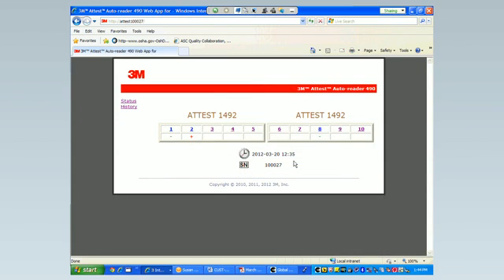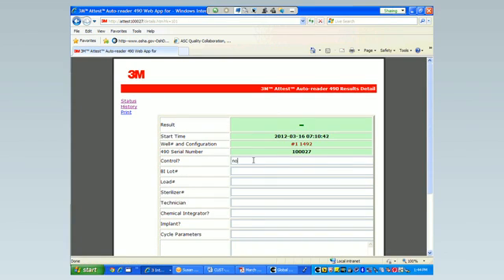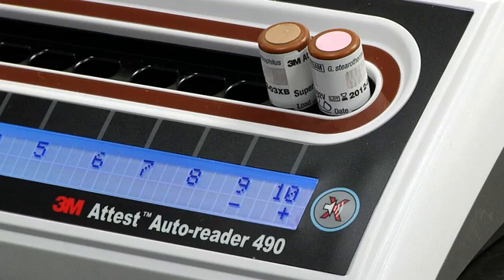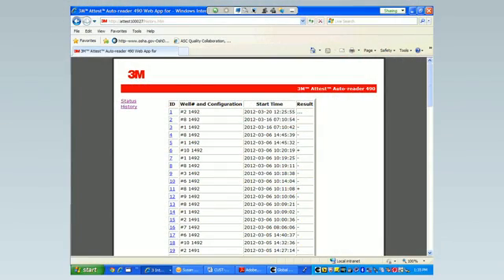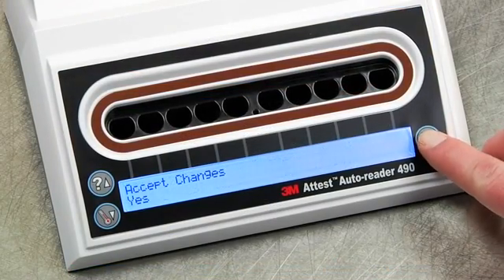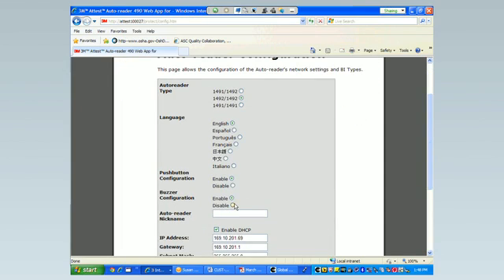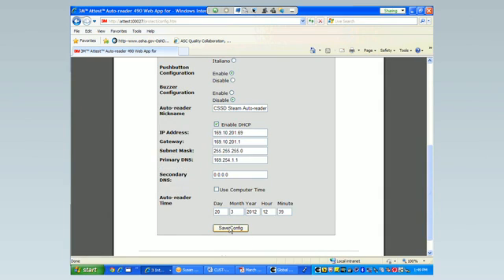The Attest web app makes it easy to create records of BI test results. After inserting a BI in the Attest Autoreader 490, open the results detail page for that BI by clicking on the corresponding well number from the status page. Enter the specific information for that BI in the empty form fields. Once the BI result is available, print or file the results detail page to create an individual record for the incubated BI. The Autoreader 490 stores results for the last 100 incubated BIs on embedded software, and the web app history page provides a summary of these results. The Attest Autoreader 490 can also be configured remotely using the Attest web app — go to the configuration page to customize the incubation wells, enable or disable the audible alarm, and assign a nickname to your Attest Autoreader 490. To learn more, see your operating manual.